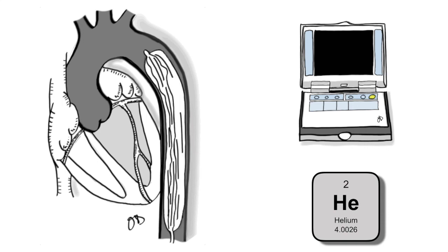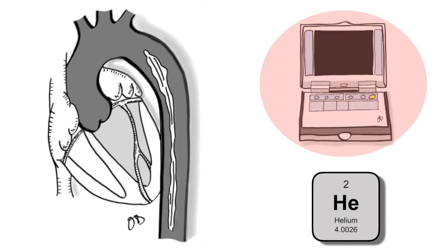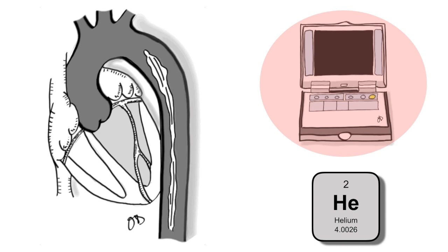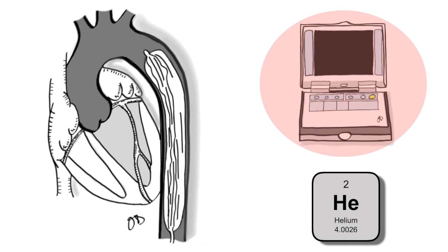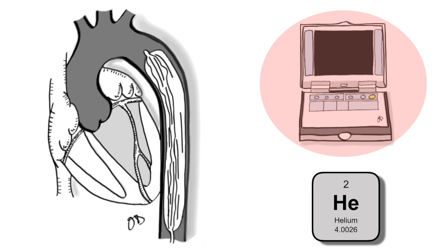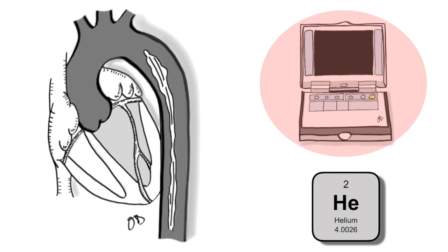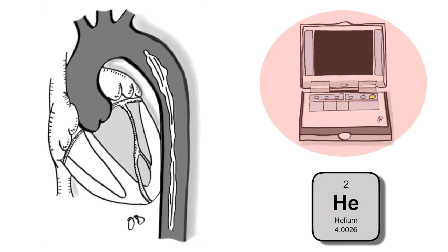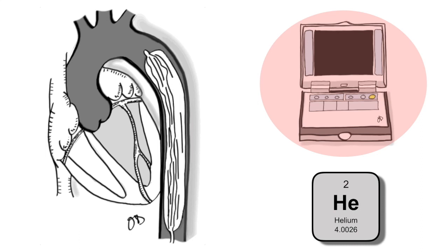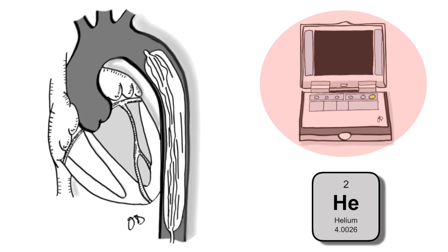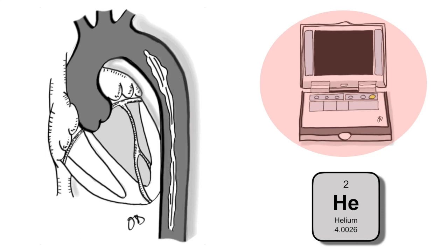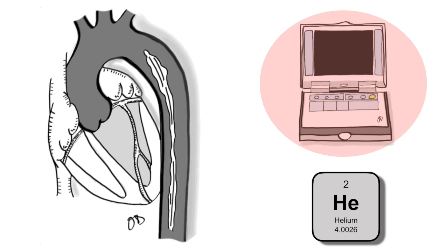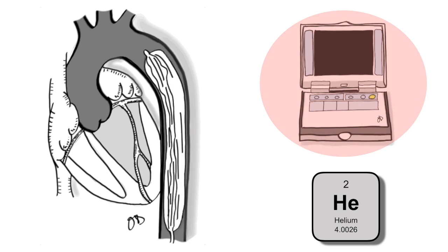The brains of the intra-aortic balloon pump is the console. It regulates the inflation and deflation of the balloon by shuffling the gas helium in and out of the balloon chamber. Helium is used because of its low molecular weight, allowing rapid inflation and deflation, and its high dissolubility in blood, mitigating the risk of emboli if the balloon ruptures.